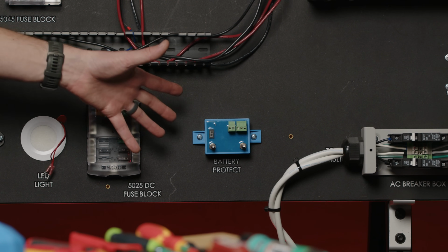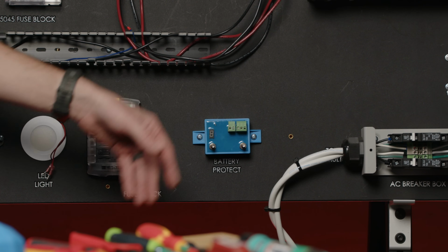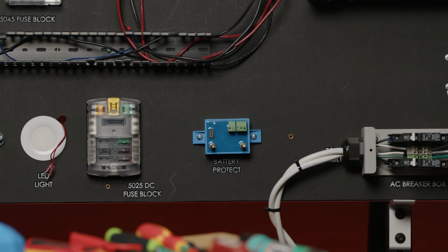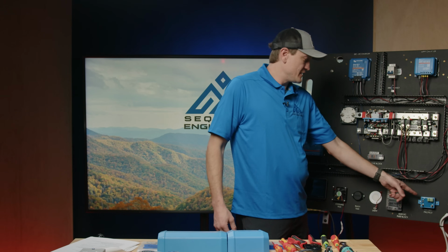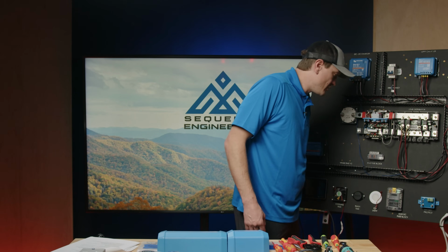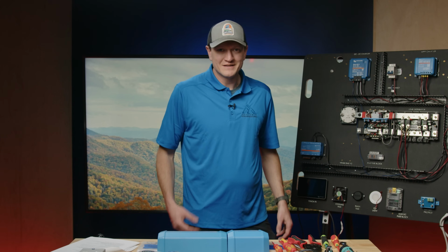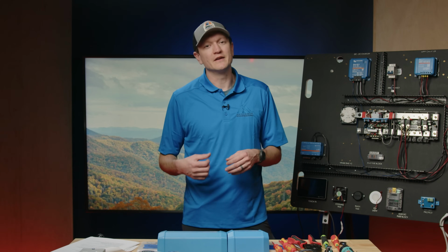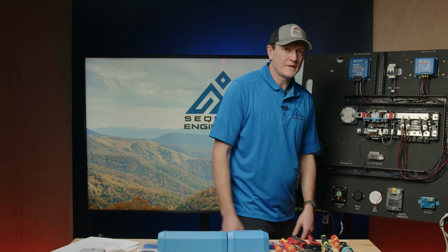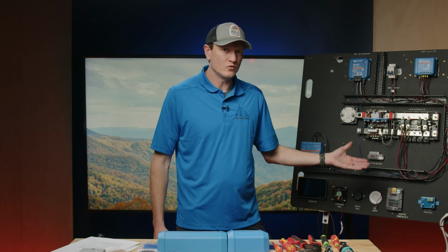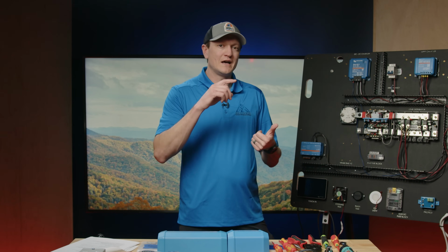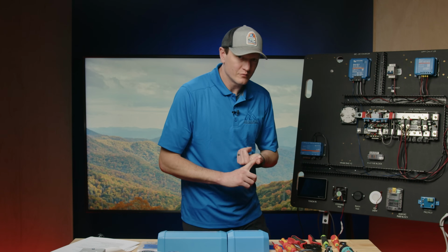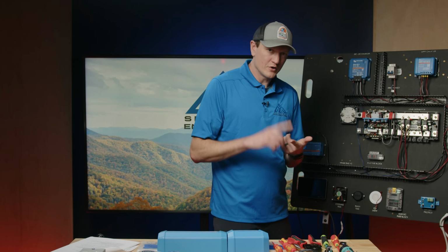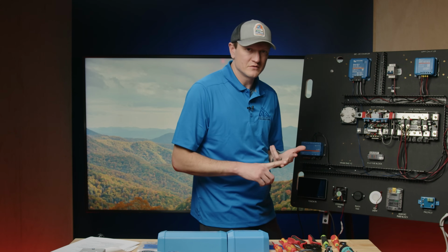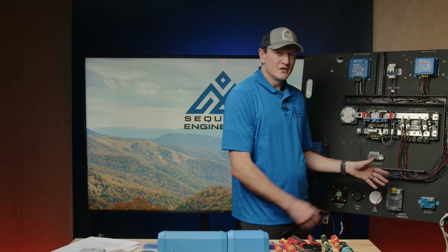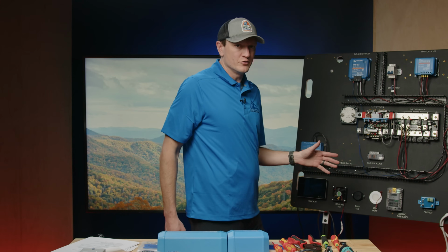Now, these devices come in 3 different sizes, okay? And they actually just added a 4th one in the 48 volt category. But this particular device comes in a 12, and a 12/24/65, a 12/24/100, and a 12/24/220. What that means is that it will work with either 12 or 24 volts, and it will allow either 65 amps to flow through it before it will destroy itself, 100 amps, or 220 amps. So you need to size that device to the amount of current that you're expecting to pass through it.